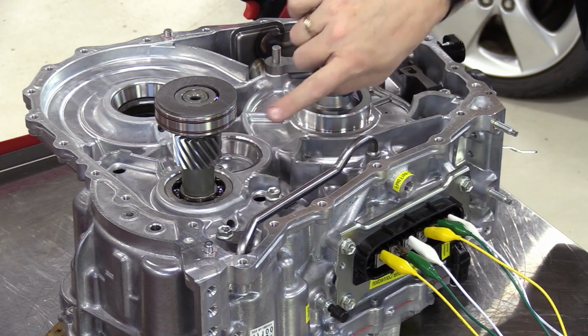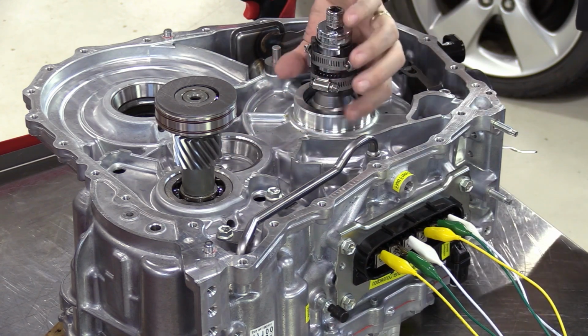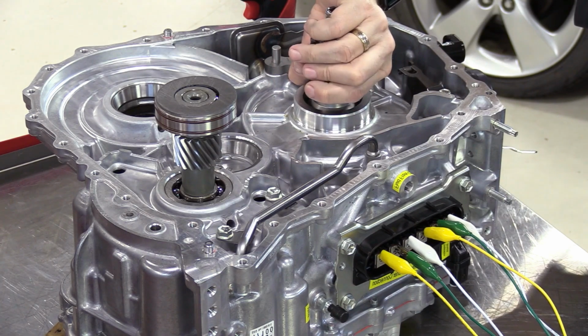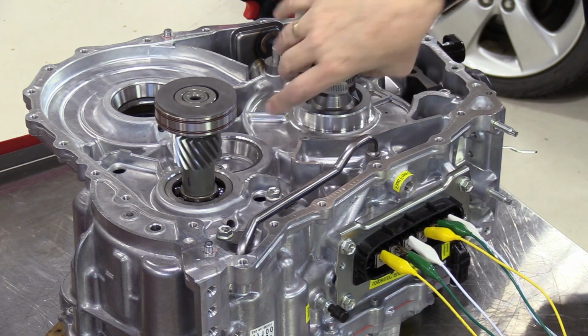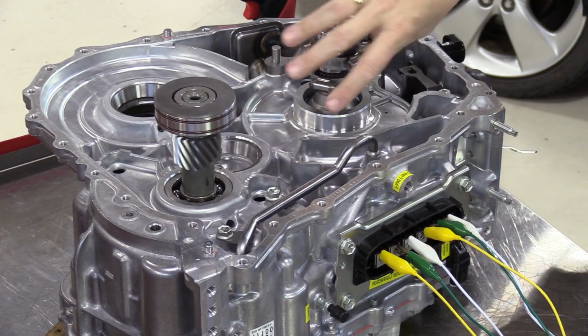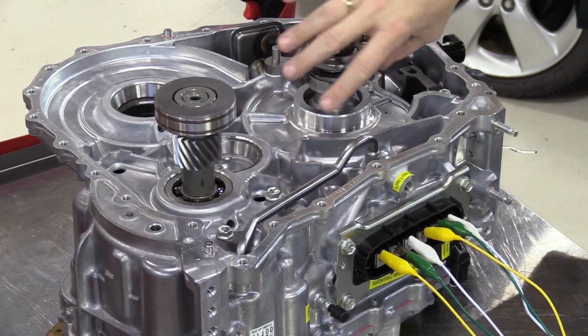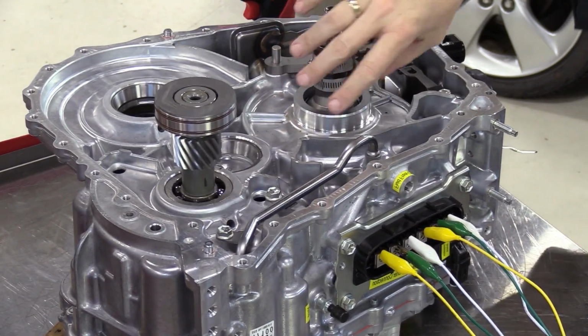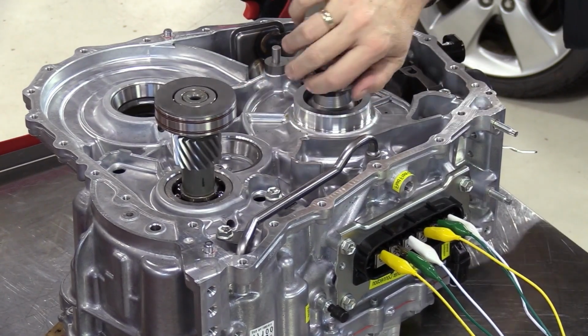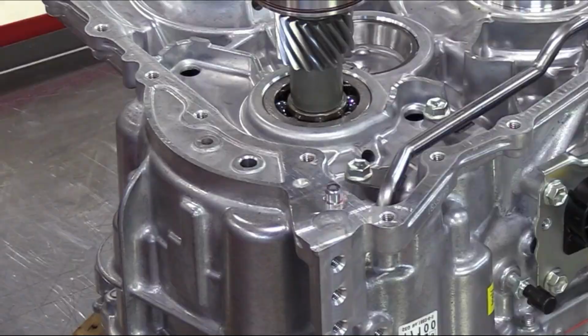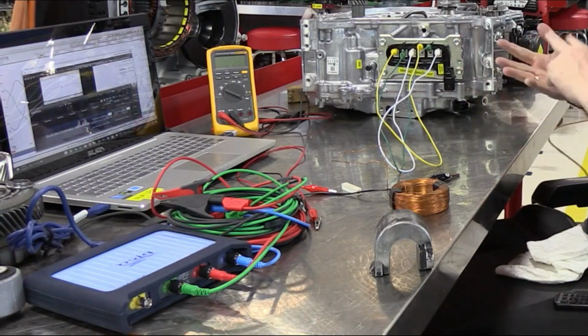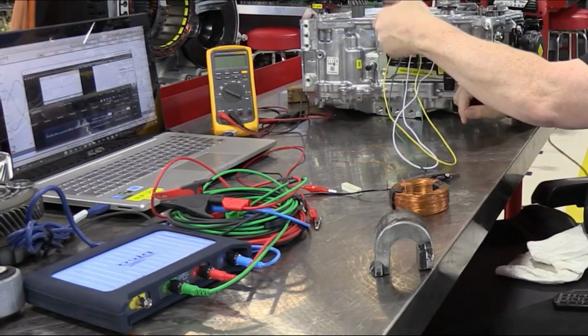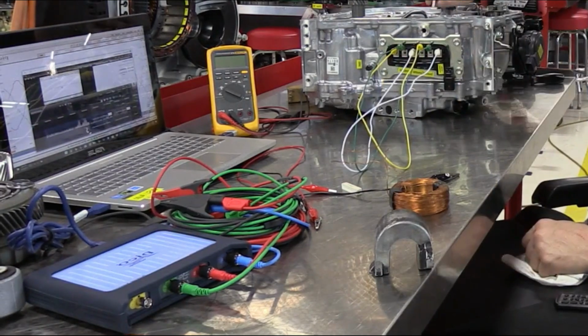If the short circuit occurs while the motor is under load, the sudden loss of torque can cause mechanical stress on the rotor and connected driveline components, potentially leading to mechanical failure. If that kind of short happens, the excessive current can blow the inverter power transistors or cause other failures in the power electronics, which totally stops the voltage supply to the motor in order to save the motor and anything related or associated with the motor.